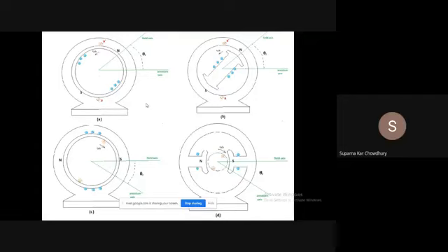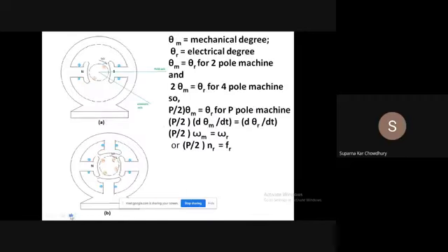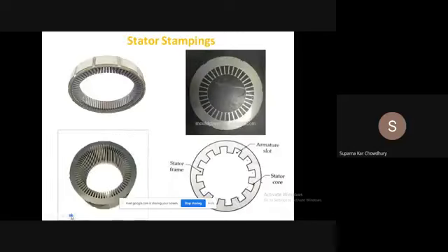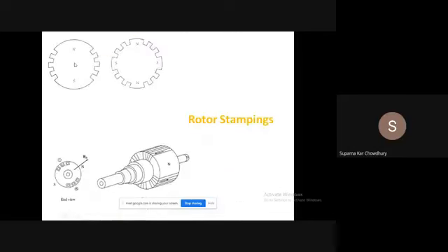Now when we go for the hydel power stations, we have the water turbines, which are slow moving devices, and the speed depends on the height of the waterfall. Now here we require a large number of poles. When we require a large number of poles, then we have to go for the salient pole construction, because just from common sense you can see how we make the poles. This is the cylindrical rotor for 2 poles.